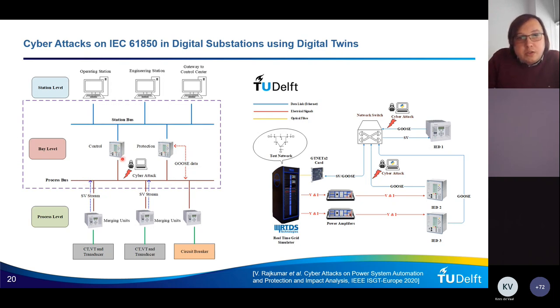And then we have various levels at the bay level of protection and control. And then at the station level, we have operating stations with SCADA in the substation, engineering workstations, and gateways to communicate these measurements remotely to the control room, to the national control centers. Now, protection devices would detect short circuits, and then by using sample values, they will send GOOSE packets to open circuit breakers. So this is, in a nutshell, how it works.